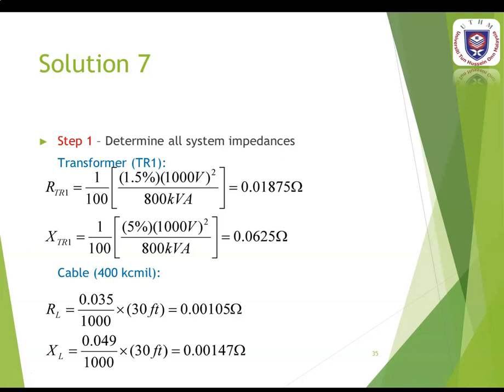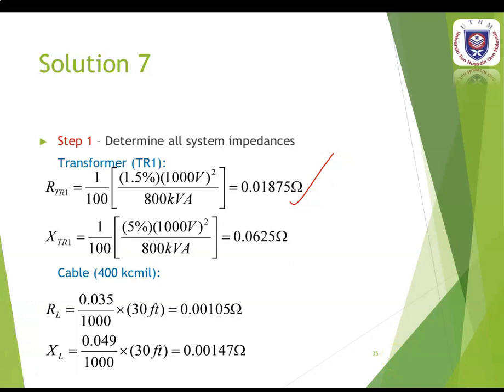For transformer TR1, using the equation 1 over 100 times resistance or reactance, times secondary line voltage squared, divided by apparent power, you can get the resistance and reactance. Remember to use the secondary voltage or the low voltage side. The resistance is 0.01875 ohms and the reactance is 0.0625 ohms.